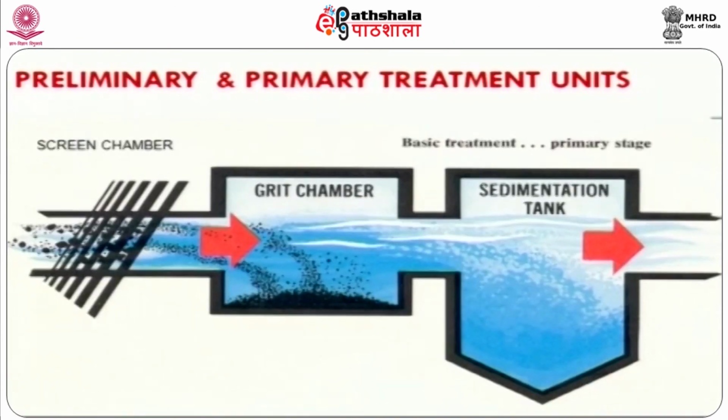So far we have discussed various unit operations as well as processes in wastewater treatment. First, we discussed various unit operations involved in wastewater treatment. Major treatments are screening activity, and the grit channel, which is normally used to remove grit particles present in the influent stream. Subsequently, we have the primary settler. The purpose of primary settling is to remove most of the suspended particles present in the influent stream. Up to the primary treatment facility, we can remove 30% of BOD present in raw wastewater.